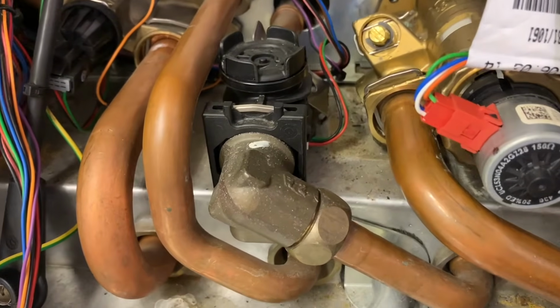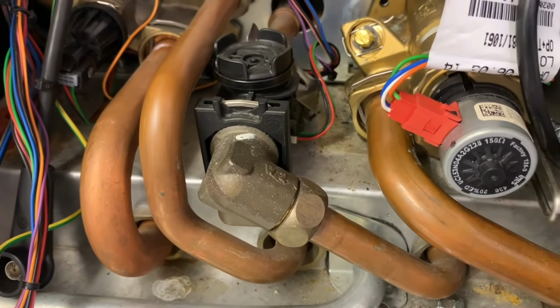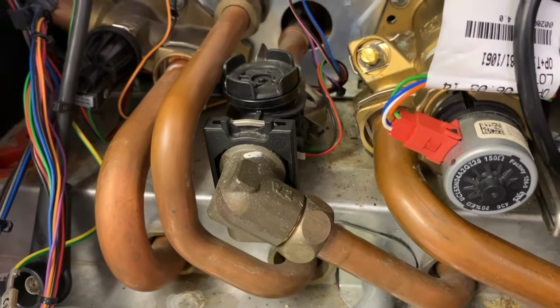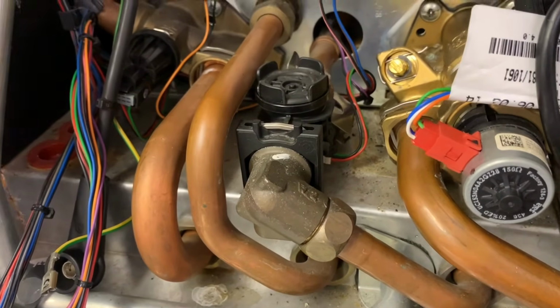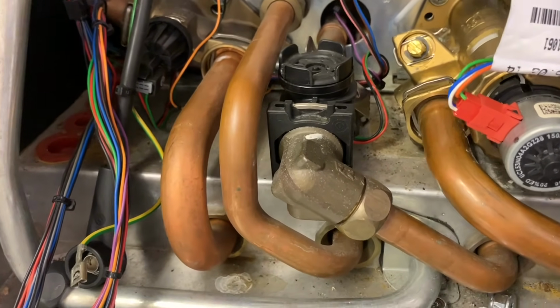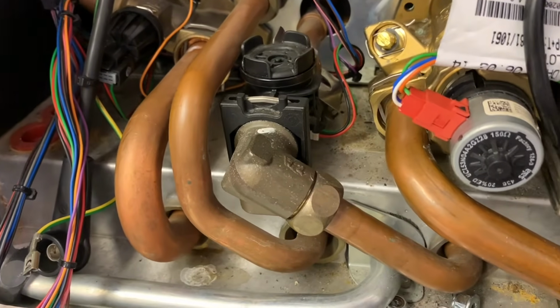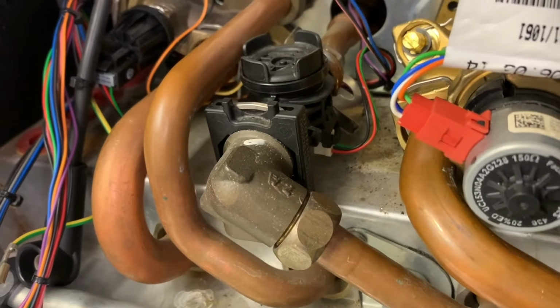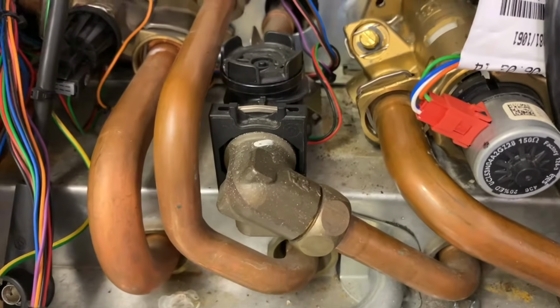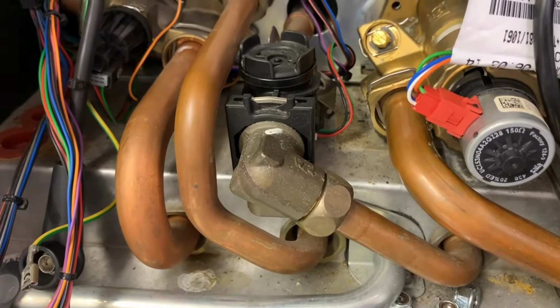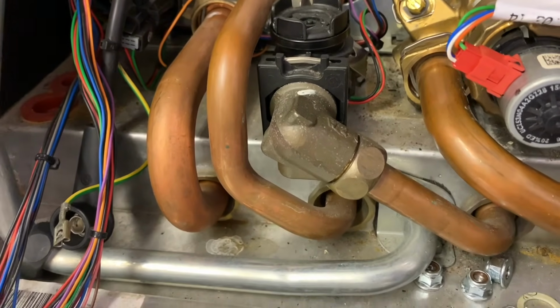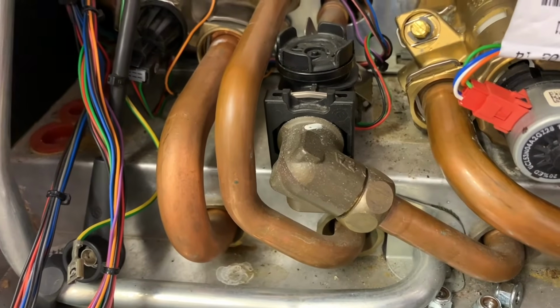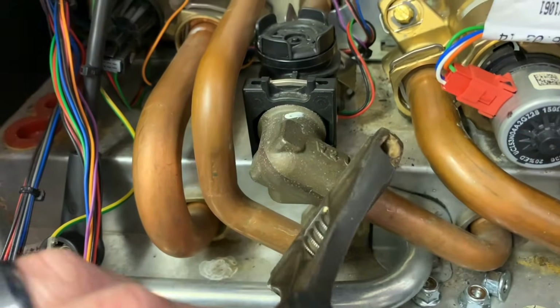Okay, next thing we're going to remove is this little puppy, which is the cold water flow turbine. What this does is, as the water passes through, there's a little turbine with a hall sensor. You can see the wires coming off the bottom of the hall sensor, but again, when we get it out, we'll look a bit closer. What that does is, it tells the boiler that there's water flowing through it. So, on the Vaillant, dead easy to take off. Just need to undo this nut first.